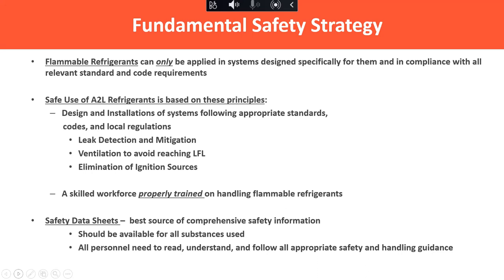The safety and handling strategy for A2Ls is grounded in a few fundamental principles. The first is that flammable refrigerants are only going to be applied or used in systems that were designed specifically to use flammable refrigerants. This is why the standards work is so important, so we can be in compliance. That will govern charge sizes.